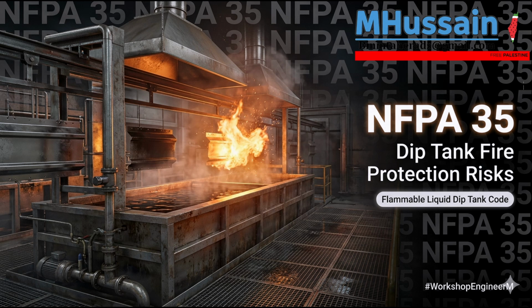Okay. But if your relief venting is set higher than 2.5 psi, the internal pressure is allowed to build to a much higher energy state before it finally releases. Like shaking a soda can before you open it. Exactly. And when it finally vents, the release is incredibly violent, pushing that explosive vapor cloud much further across the property. Wow. So because of that physical thrust, the standard mandates you multiply the setback distances by 1.5. So that 30-foot setback immediately becomes 45 feet just because of a vent setting on a valve.